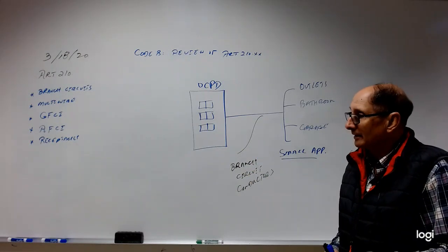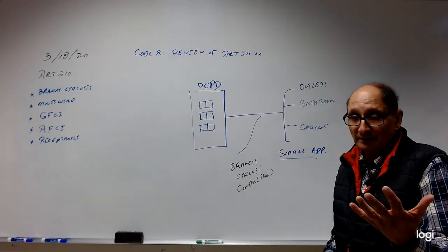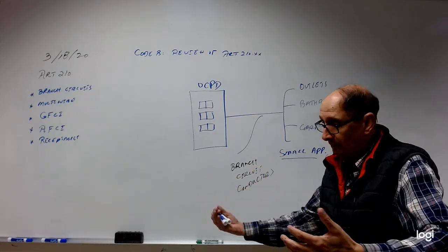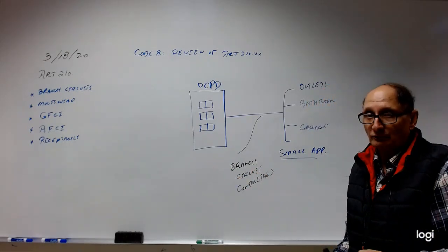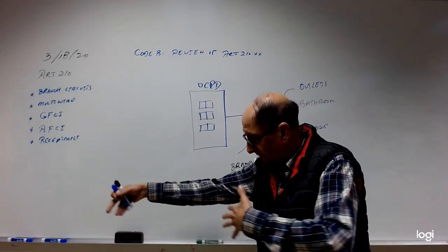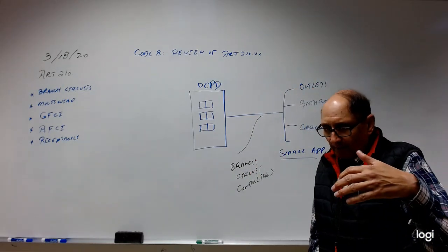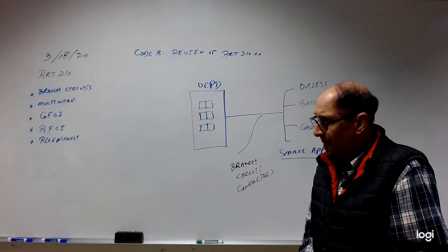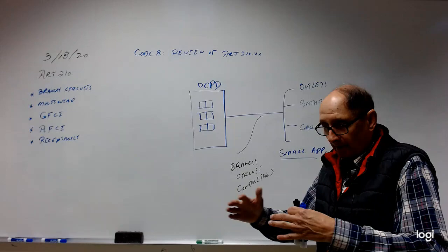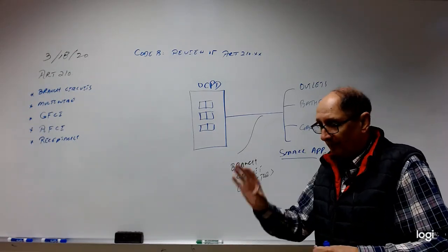And then the last one, again, receptacles, which we just finished in previous videos. You have general purpose receptacles that are required within 6 feet of your entrance when you walk in through the door, and 12 feet thereafter, with one exception, as long as the wall space is 24 inches long. Now, how do we define wall space? Any space that is a minimum of 24 inches long, unbroken space: no barriers, no sliders, no moving parts, fixed.